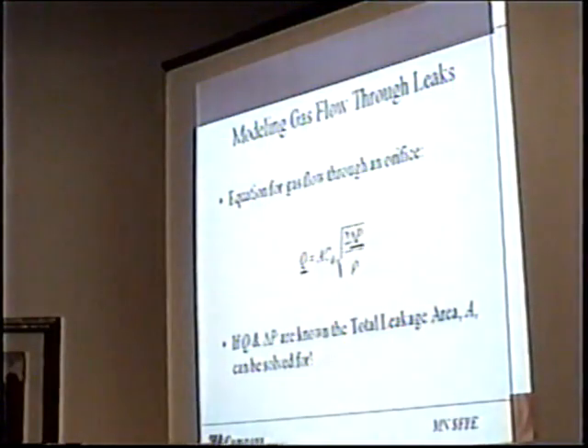And we already know our flow rate Q and our pressure differential just from the test. And then we've got some givens: our coefficient of discharge, empirically based, which has been found ahead of time. We also have our density, which is just the density of regular atmospheric air here. So essentially we can solve for our area, no problem.